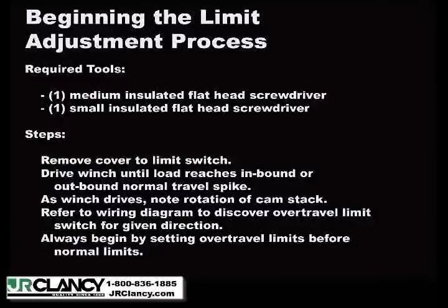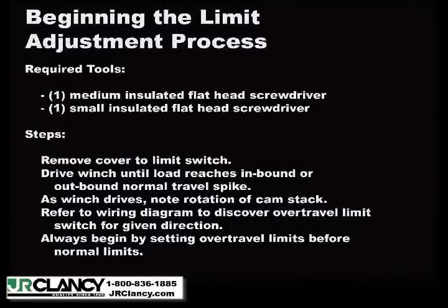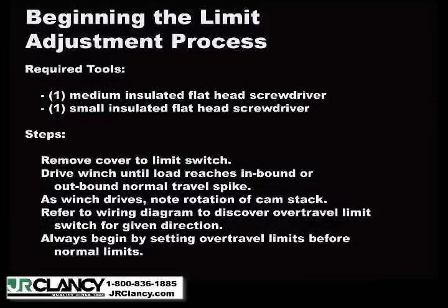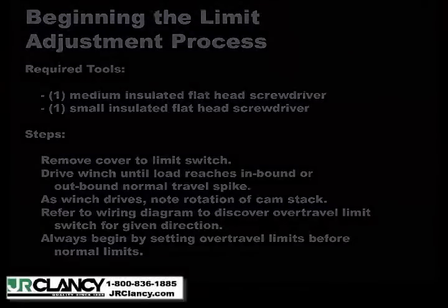Begin by removing the cover to the limit switch. Drive the winch until the load reaches the inbound or outbound normal travel spike. As the winch drives, note the rotation of the cam stack. Refer to your wiring diagram located under the cover to the limit switch to discover the over travel limit for the given direction. Always begin by setting over travel limits before normal travel limits.